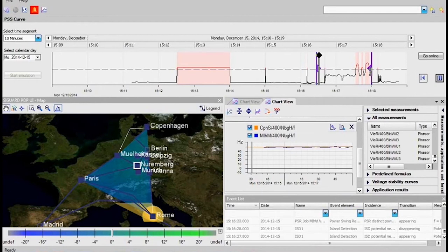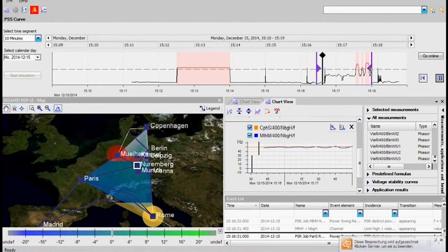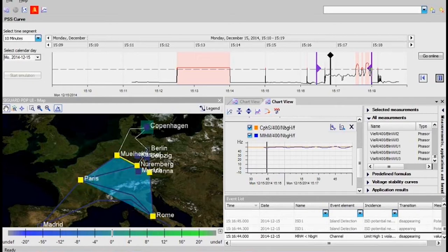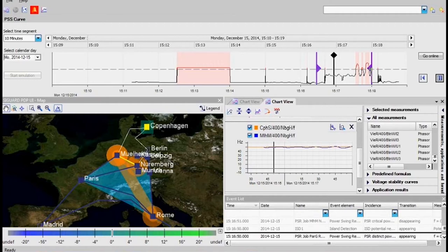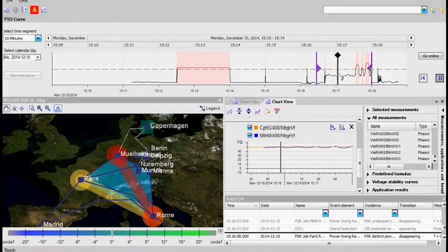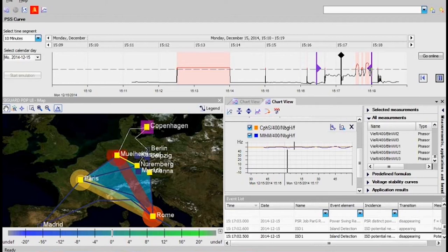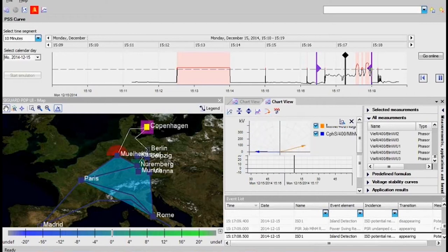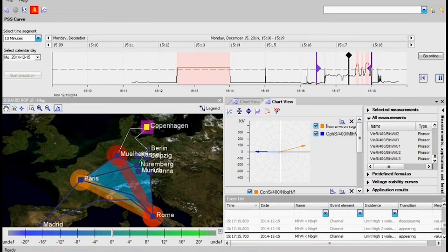Here, on this graphic, you will see the user interface of SIGUARD PDP. The highlight of this user interface is the visualization in real time. On the top, we see the power system status curve, which is a kind of fever curve of the network. Violations of defined limits are indicated in red colored areas. A map with a colored scheme overlaid on a geographical map shows, for example, violations of limits in voltage, current, angle differences, power swings, and islanding conditions. In the center, we see a chart view and a vector diagram. On the right-hand side, we have a list of all measurements available in this monitored system. The bottom shows the event list with microsecond-exact timestamped information.